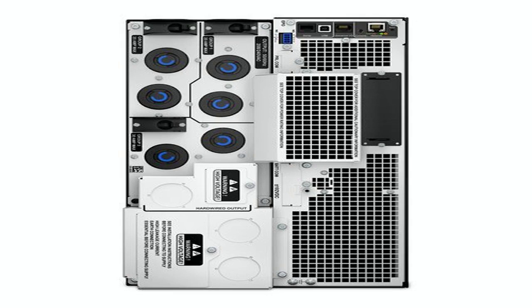The leak-proof design also makes it a good fit for environments that are less than pristine, data halls in older buildings, facilities with air conditioner condensation issues, or even telecom closets on the street level where rain can make its way in. Conversely, if you're a solo freelancer working from a home office, or you have a small business router and a couple of NAS devices that can tolerate a few minutes of outage, you're probably overspecifying. A line interactive UPS in the 500 VA range would cover you at a fraction of the price and with a lighter footprint.